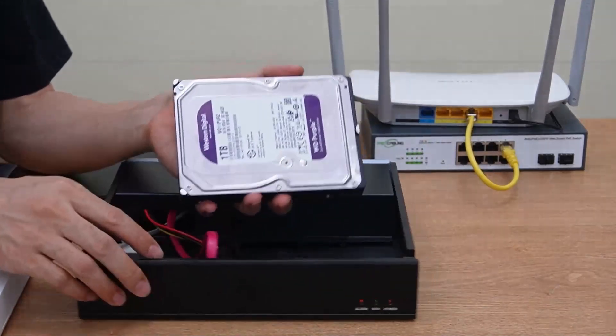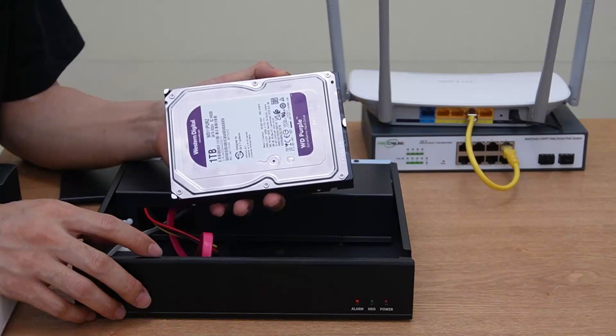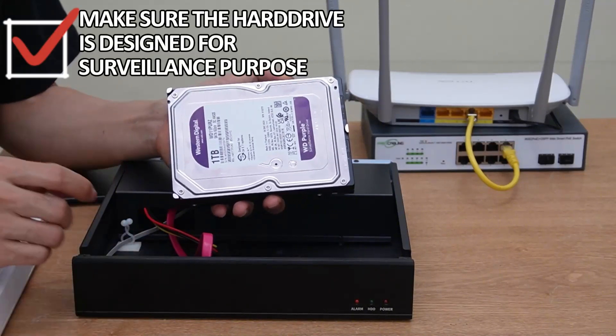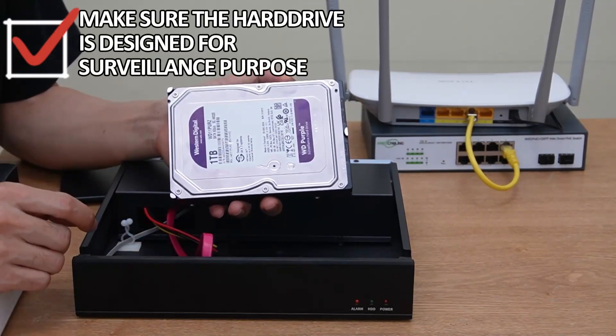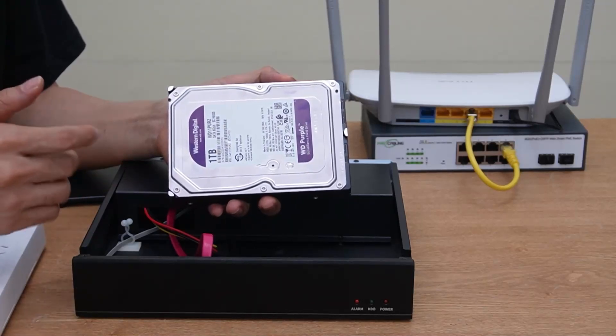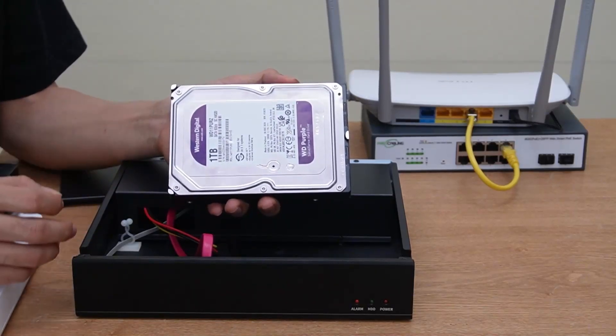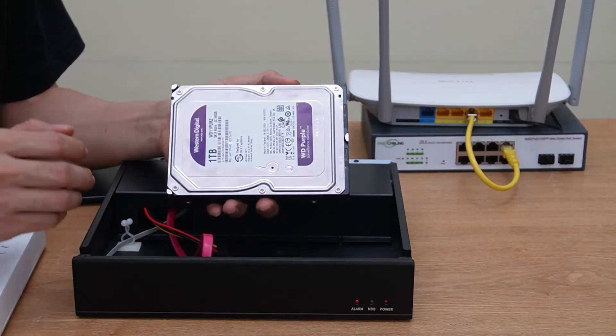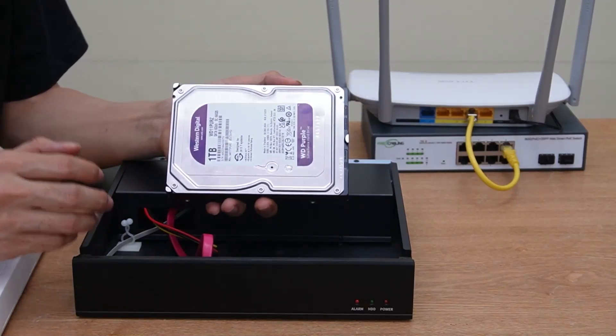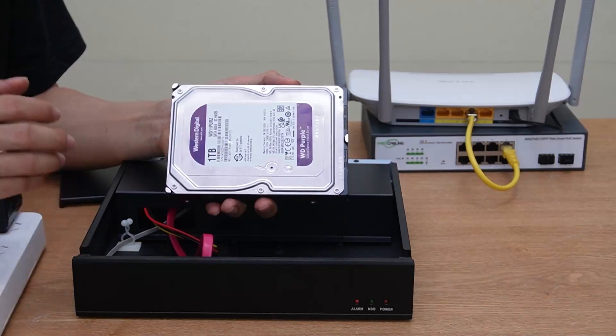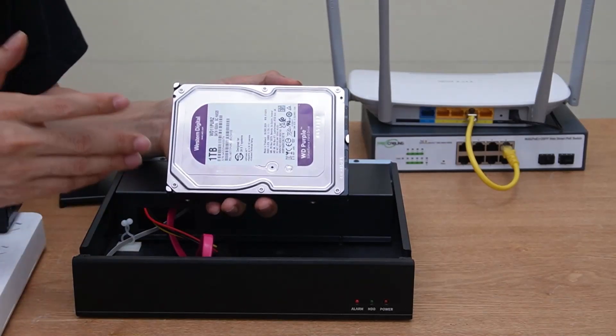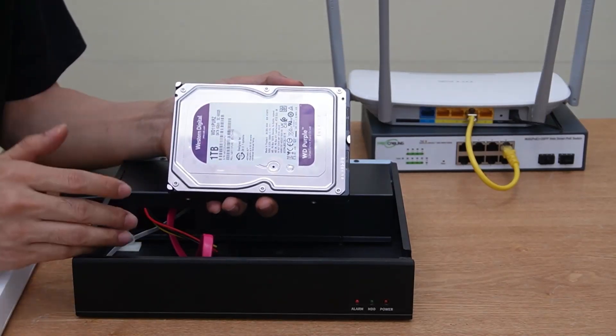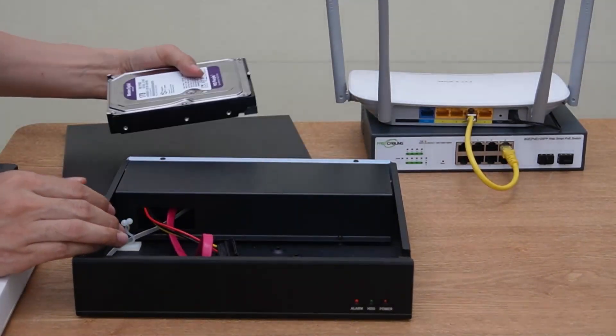We need to install this hard drive. When we pick the hard drive, make sure the hard drive is designed for the surveillance purpose. The producer has produced different kinds of hard drives. If the hard drive is designed for the PC, they didn't expect you are going to put the hard drive running 24x7 and it has such heavy data write into the hard drive every second and every minute.